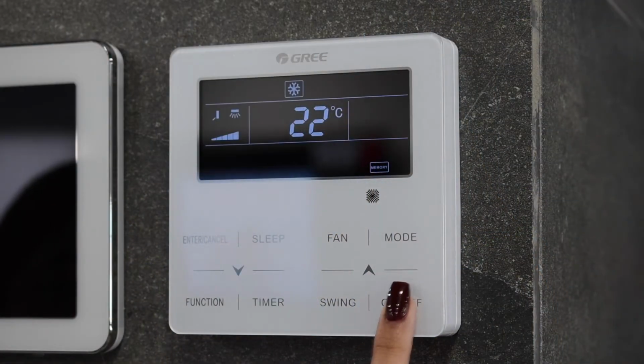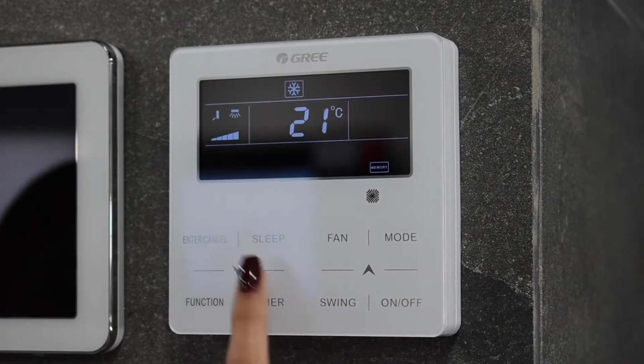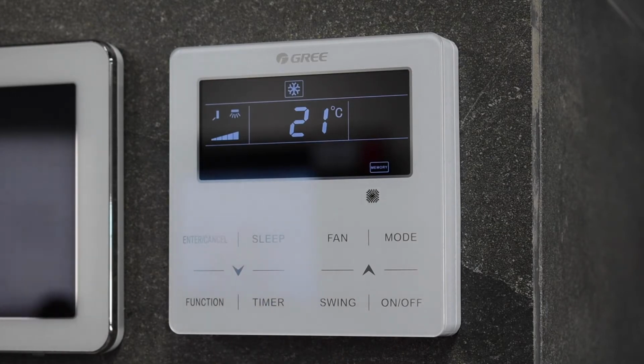To reduce energy wastage, a BMS can automatically or through alerts control the HVAC system for optimal climate conditions when required, as well as control lighting. Integrated room controllers form a part of the BMS and can control and schedule the classroom temperature. To improve efficiency further, additional equipment can be added and controlled by the BMS, including occupancy sensors, so the HVAC and lights respond to the actual number of people present in the room.